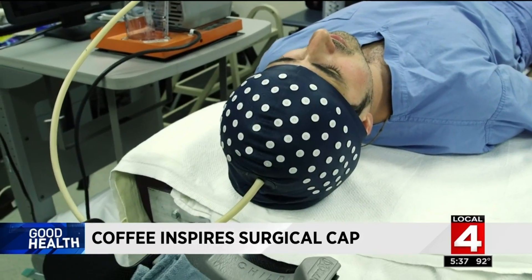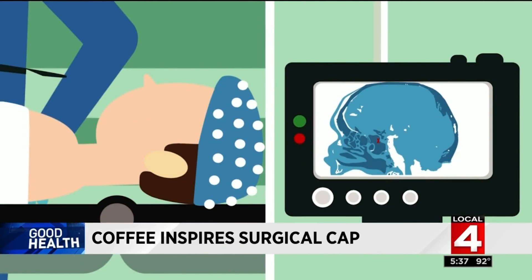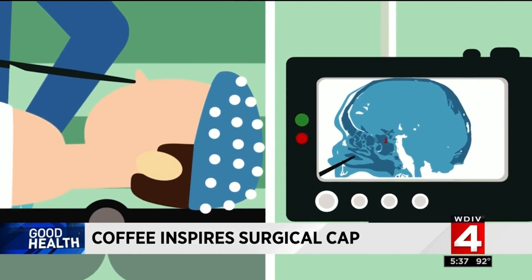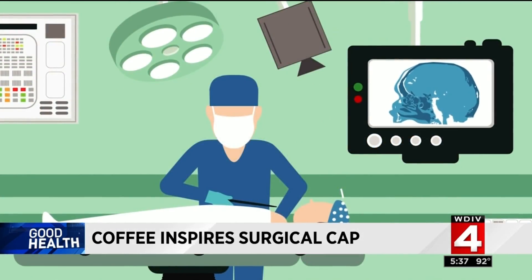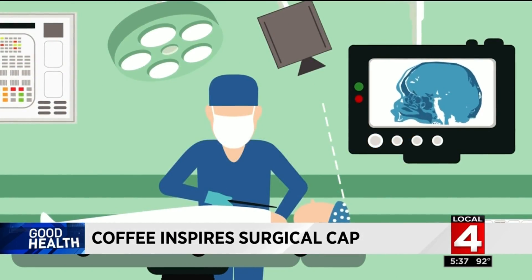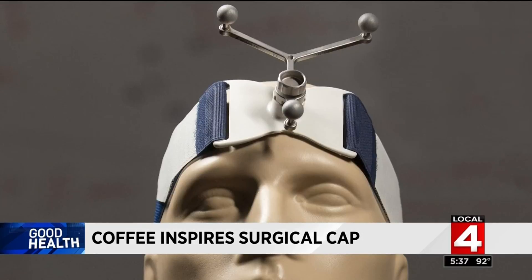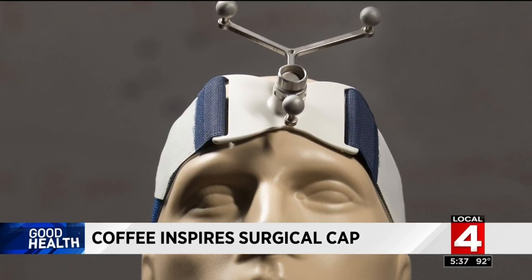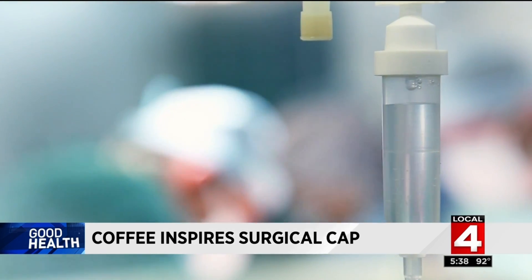Firmly attached reflective markers and an optical scanner set up a surgical GPS display to guide doctor's tools inside the patient. It holds the markers very rigidly on the head so that they can't move — you can move the head all around and those markers go just with the head. Tracking head movements is a problem with the current system, an elastic headband with double-stick tape. The skin is mobile and doesn't stick to the skull, so a very slight motion can throw us off. A quarter inch can be a big difference when you're operating in a really tiny area.